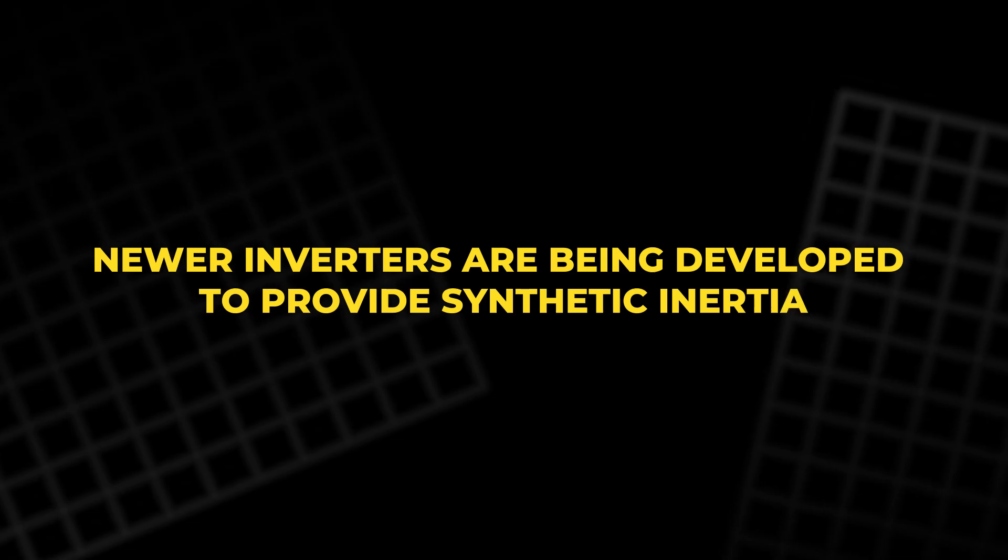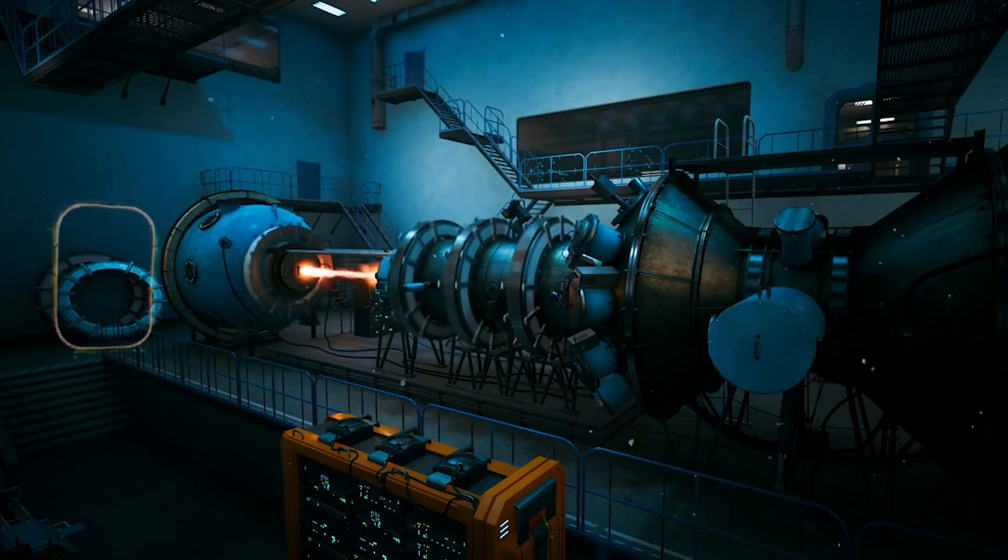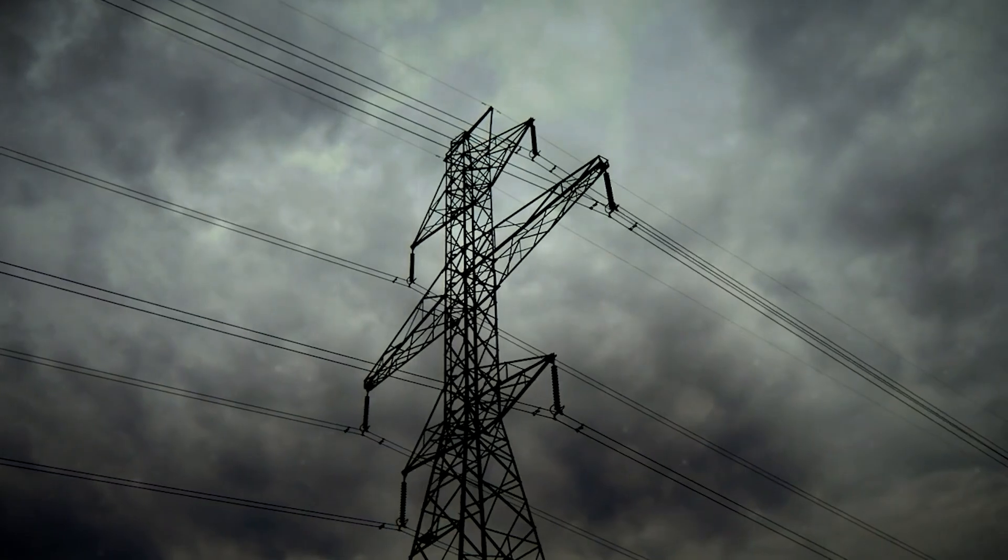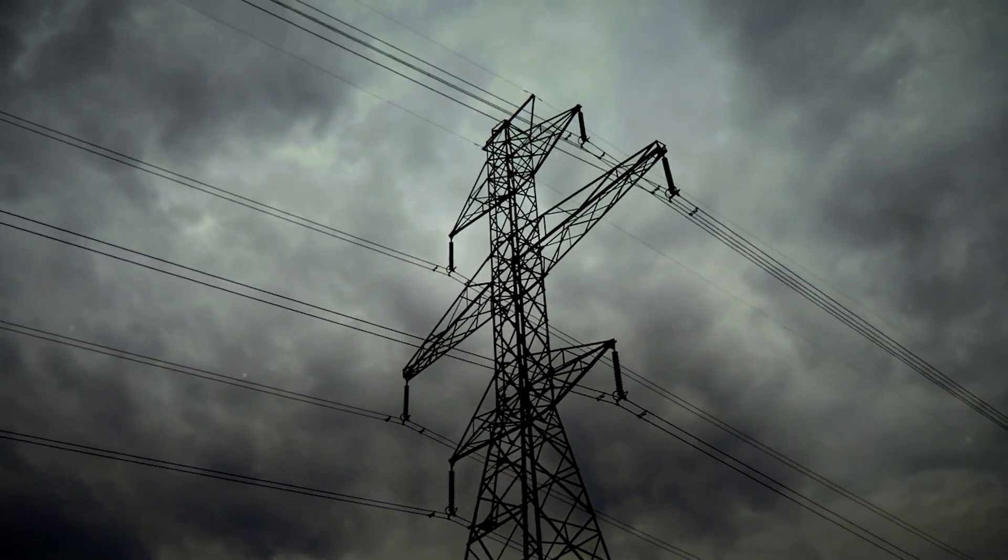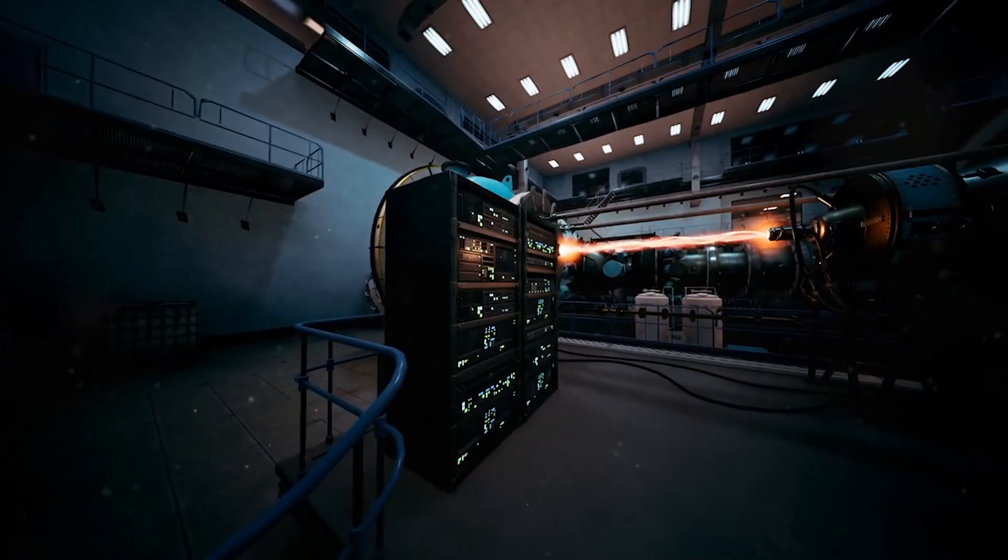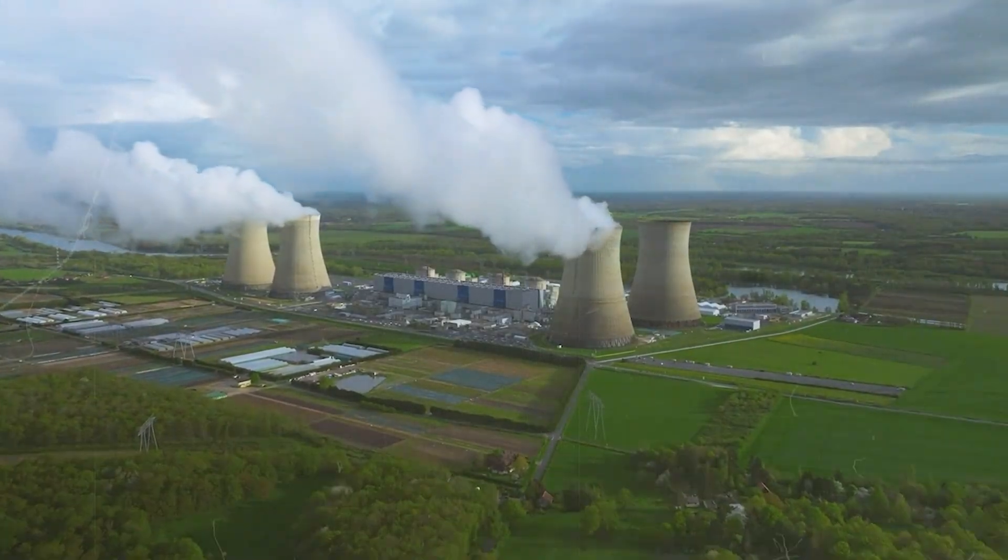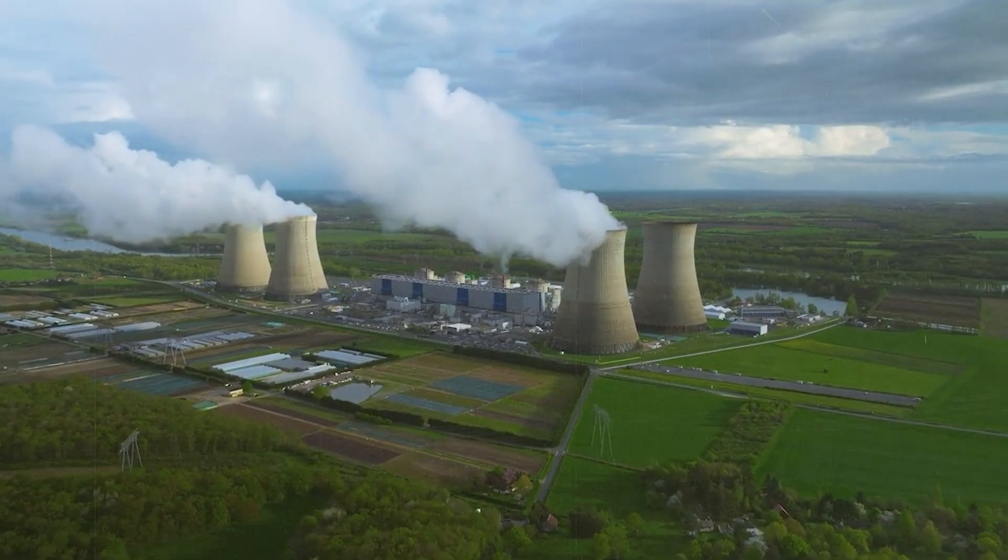To address this, newer inverters are being developed to provide synthetic inertia. This means that the inverter can simulate the behavior of a large spinning generator, helping to stabilize the grid during disturbances. While these inverters can help address some of the challenges of integrating renewable energy, they still cannot fully replace the inertia provided by traditional power plants.